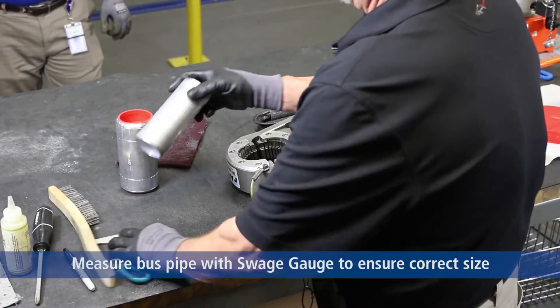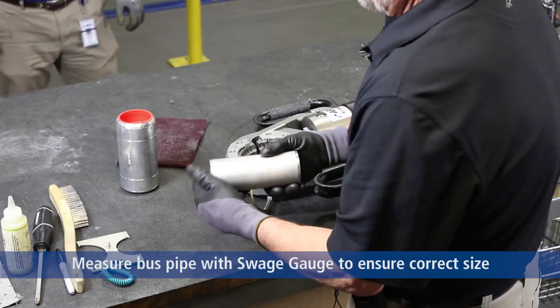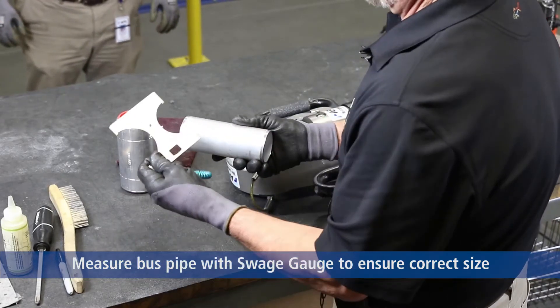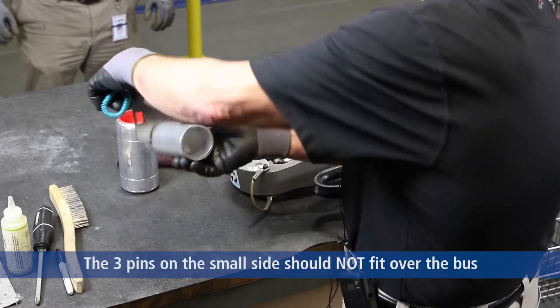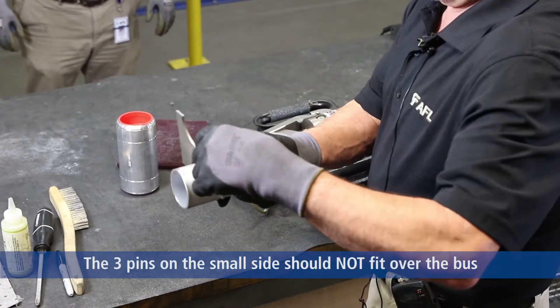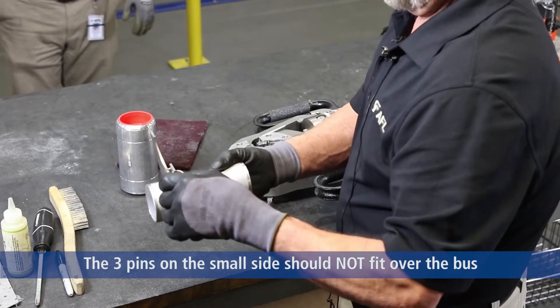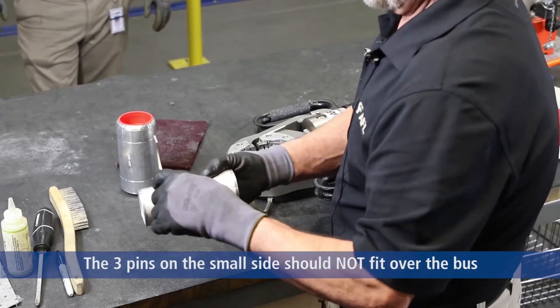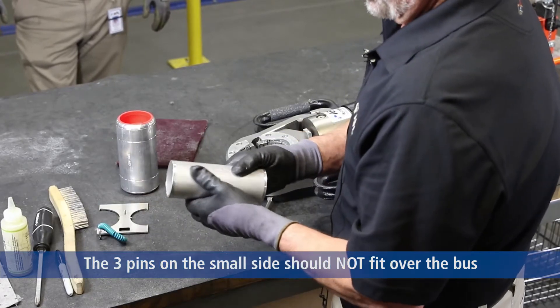We're going to take a two-inch piece of bus — it's extruded aluminum pipe — and measure it with our swage gauge. The small side will not fit two-inch bus. If it fit the bus pipe, then you would have something smaller than two-inch, and it would not work in our system because our system works in outside diameters.